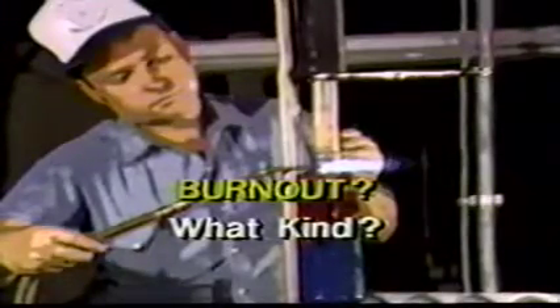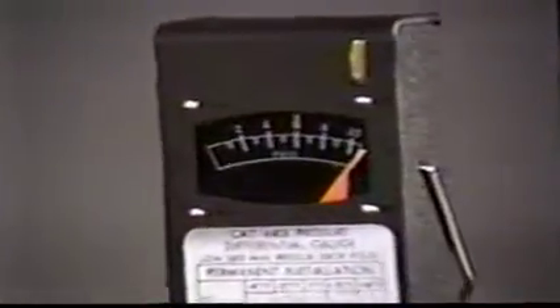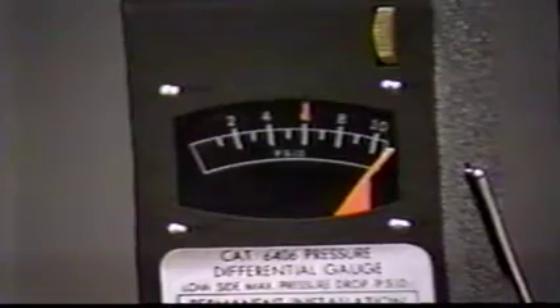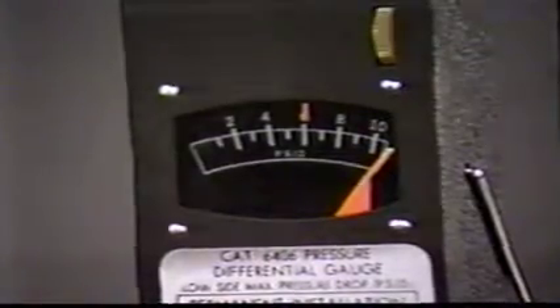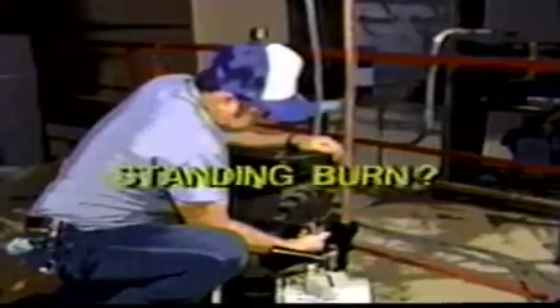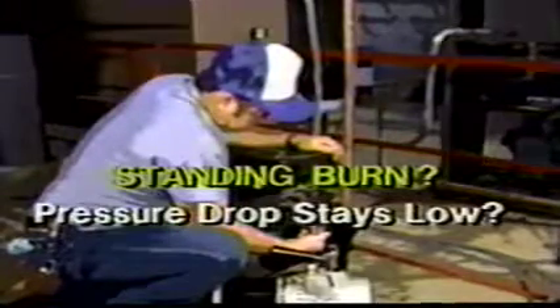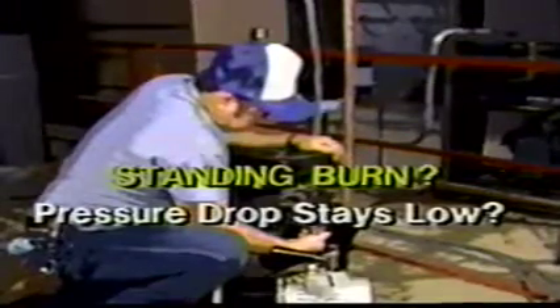The dryers selected should be as large as possible and must be replaced as long as their pressure drop exceeds allowable limits. In the case of a standing burn, where contamination has not been pumped out of the compressor, it may not be necessary to replace the first suction line dryer used. If a large enough filter dryer was installed and the measured pressure drop remains low across it, the dryer may be left in the system.